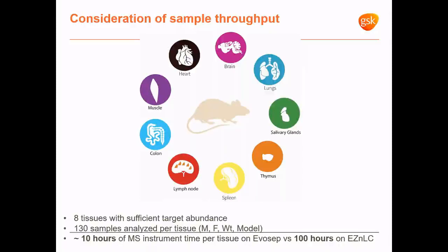10 hours is definitely a feasible commitment to an effort. I wouldn't expect significant change in state in the instrument over that short of time, whereas over 100 hours, there might be a more significant drift and shift in platform stability issues. So I think that this coupling is really quite ideal for this kind of effort.